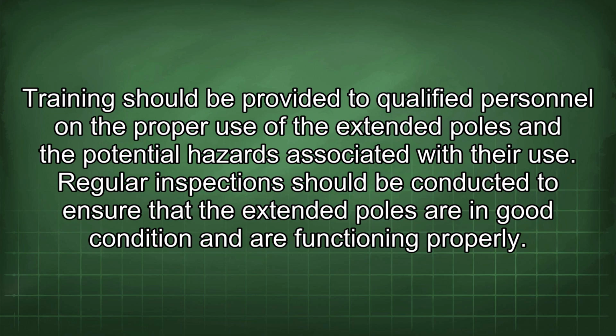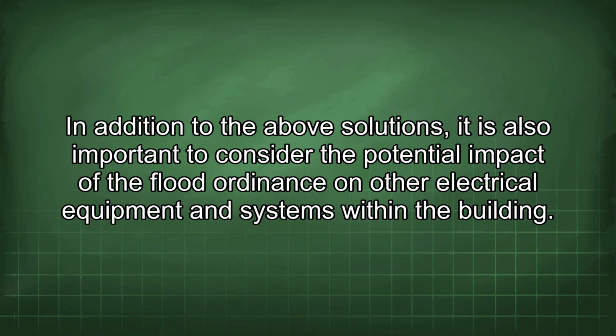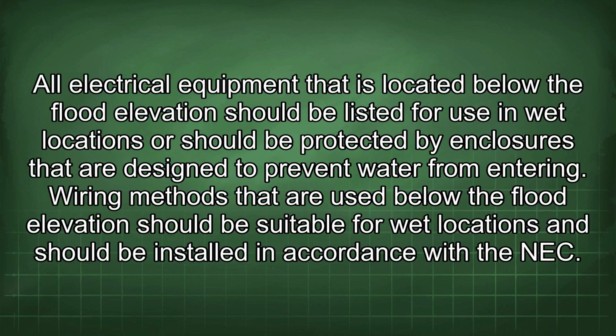In addition to the above solutions, it is also important to consider the potential impact of the flood ordinance on other electrical equipment and systems within the building. All electrical equipment located below the flood elevation should be listed for use in wet locations or protected by enclosures designed to prevent water from entering. Wiring methods used below the flood elevation should be suitable for wet locations and installed in accordance with the NEC.